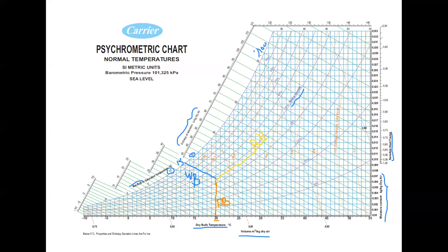And then we have humidity ratio, which is the easiest. All you need to do is to continue these horizontal lines to the right. And as you can see, this is between 0.006 and 0.007, which we normally take the middle, which we say is probably 0.0065 or 68. That's up to you. So this one is humidity ratio. That's how we can find humidity ratio.